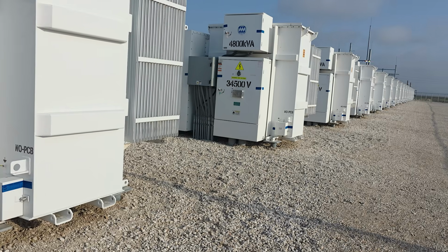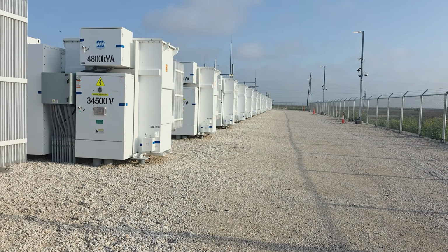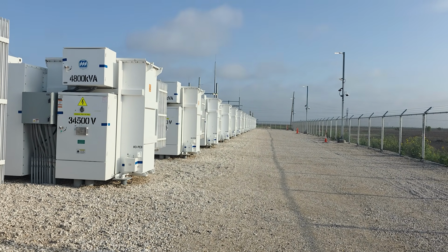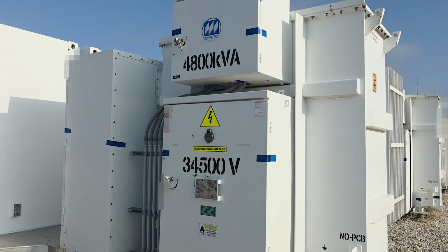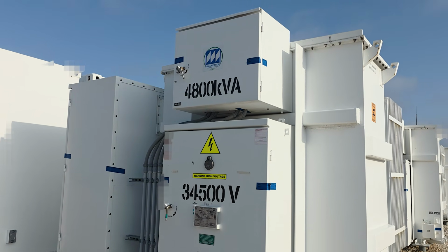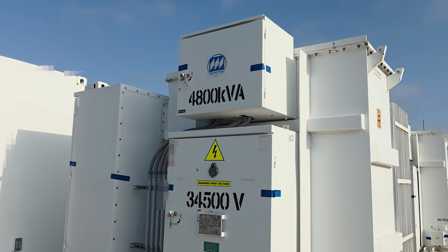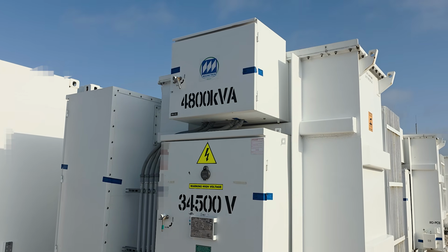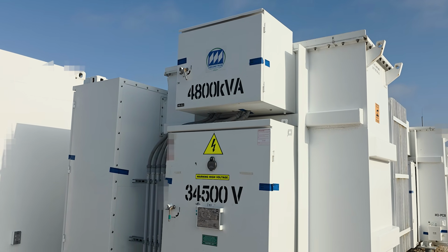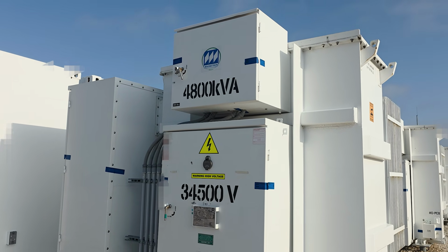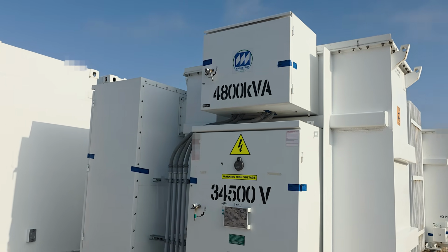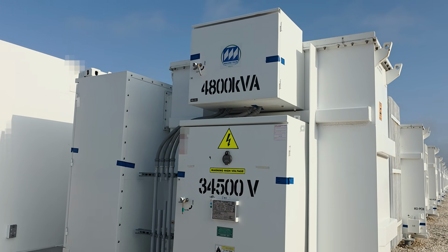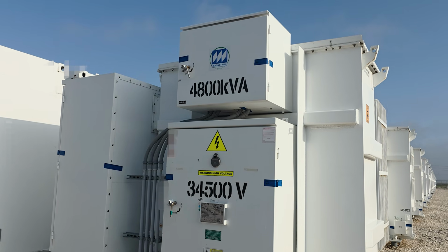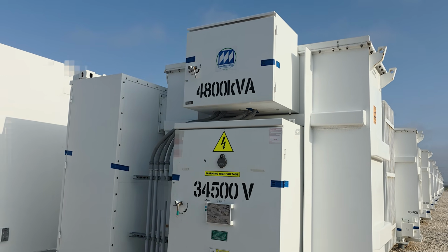So I believe there are 3 or 4 circuits in this particular run, bringing power back to the substation. This particular customer is very tech savvy, so they have added a lot of extra equipment in this transformer. Generally, transformers are a dumb device. There's no electronics installed in them or on them. It's simply windings and a coil, and that's how you get your transformer.